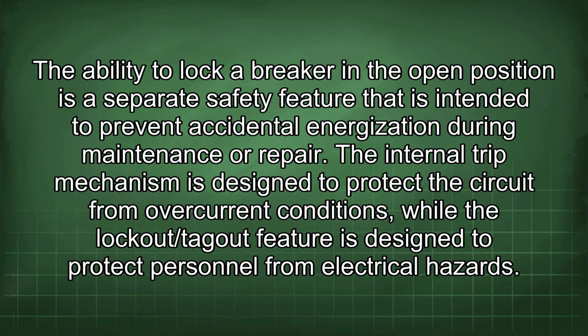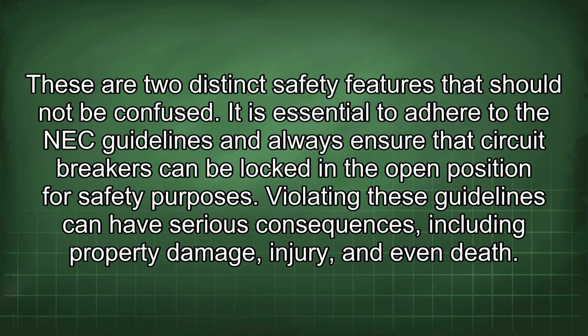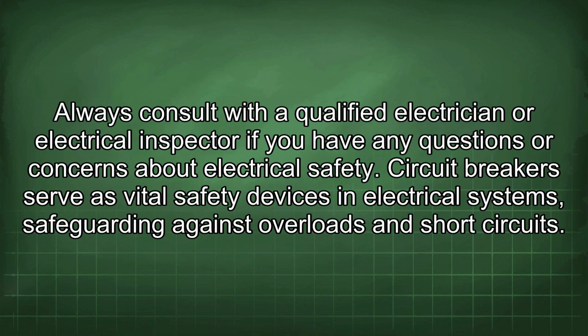The internal trip mechanism is designed to protect the circuit from overcurrent conditions, while the lockout/tagout feature is designed to protect personnel from electrical hazards. These are two distinct safety features that should not be confused. It is essential to adhere to the NEC guidelines and always ensure that circuit breakers can be locked in the open position for safety purposes. Violating these guidelines can have serious consequences, including property damage, injury, and even death. Always consult with a qualified electrician or electrical inspector if you have any questions or concerns about electrical safety.